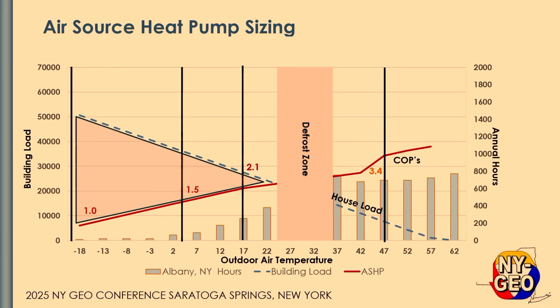So you can see if you size for cooling, you have a fairly high balance point here of maybe 22 degrees, and so you've got electric heat required in this triangle. Now there's not a lot of hours down here, but from a utility perspective, having electric heat turn on is a demand that is a problem from the generation standpoint, and so that is really something we're going to try and take a look at.